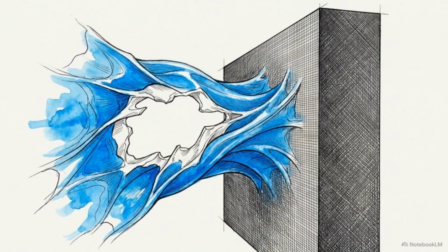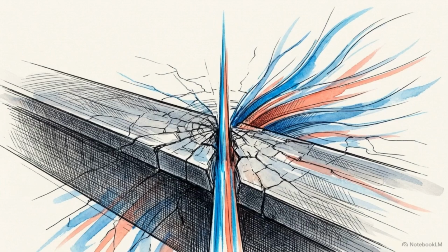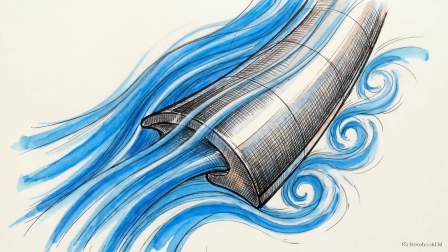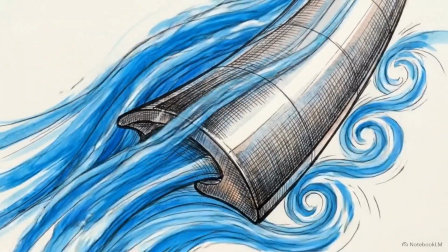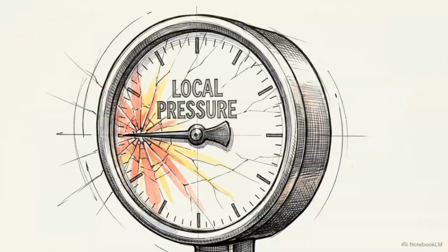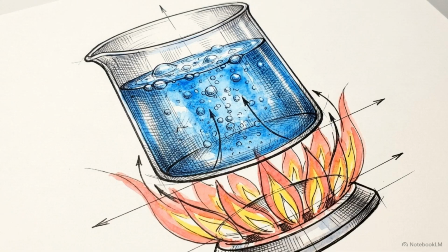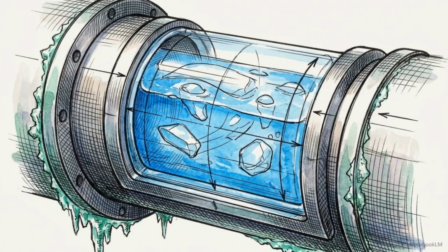These pits are the result of distributed liquid motion losing its continuity under low pressure, then violently rebuilding itself through mechanical force. When liquid accelerates around a narrow valve or the curved side of a spinning blade, it redistributes local pressure and velocity. Flow that moves fast enough eventually spends its entire local pressure budget. Unlike boiling, which requires adding heat until molecules escape, this flow reduces external pressure so suddenly that vapor pockets can survive in relatively cold liquid.